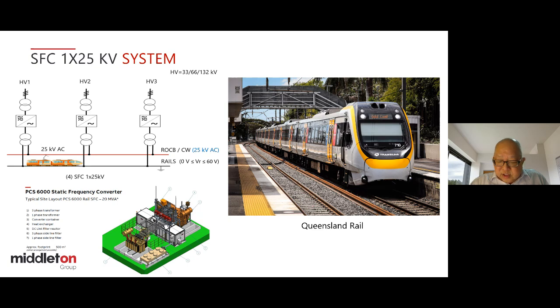And SFCs have a shorter design life of something like 30 to 40 years compared with transformer-based systems. Also, don't forget, the cooling system needs to be rebuilt or replaced every 15 years. See the Lego-looking thing sitting on top of the green block, that's your cooling system. It will need to be replaced or rebuilt every 15 years, and what it means is your SFC will need to be shut down. So if you're adopting this solution, make sure you have enough SFCs on the system to allow for an N-1 situation and still allow the train operator to run the full service under N-1. And also under N-2, when you have 2 units down, you are still required to provide enough power for the operator to run a reduced service, acceptable and negotiable with the train operator.